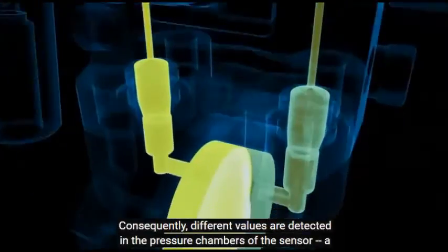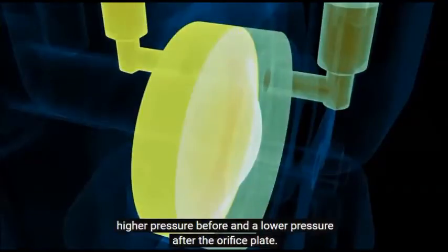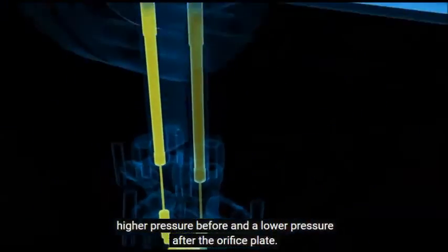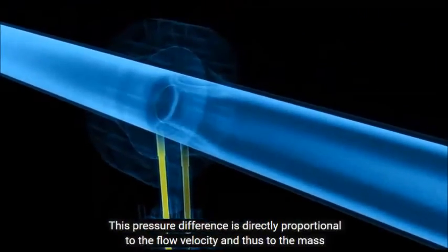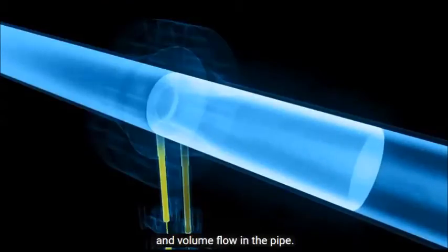Consequently, different values are detected in the pressure chambers of the sensor, a higher pressure before and a lower pressure after the orifice plate. This pressure difference is a direct measure for the flow velocity and thus the mass and volume flow in the pipe.